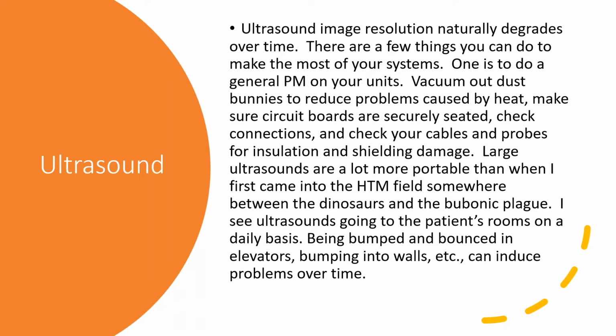And each probe, I think, was like $1,800 to $2,000, somewhere in there. And so these machines now, let's say you repair 1 probe apiece for all 15. And now they are performing as good as they ever have. And so until we can get them replaced, this is as good as it can be for that platform. And we've got 9Es, some 10s, some Epics. We've got all kinds of stuff, but every one of them is now up to as good as it can get until we get some more money.